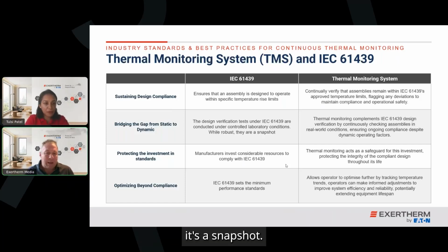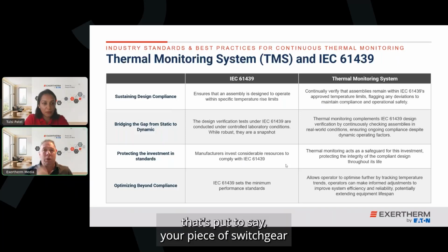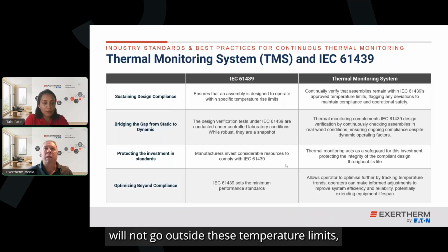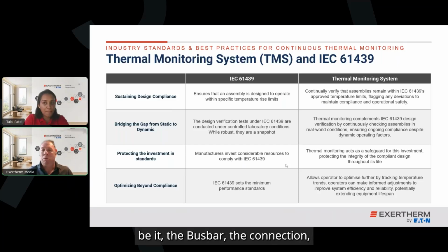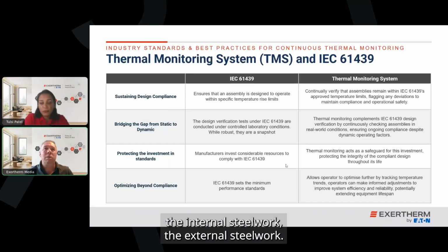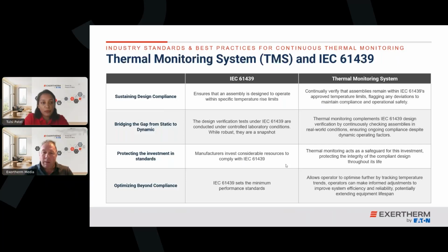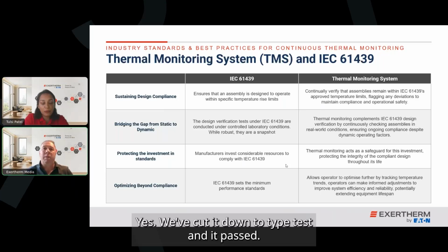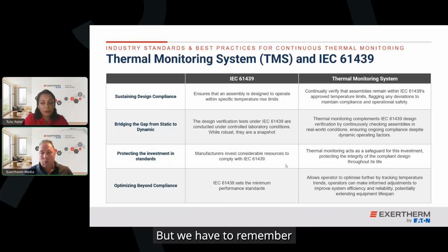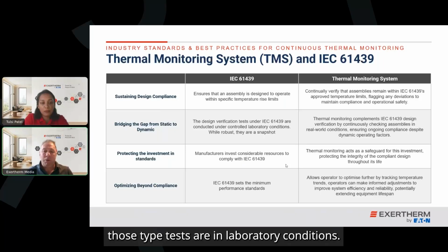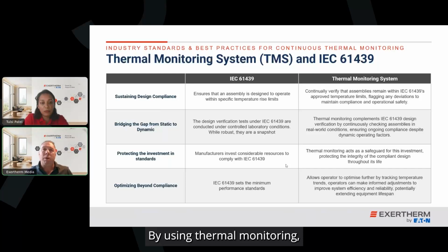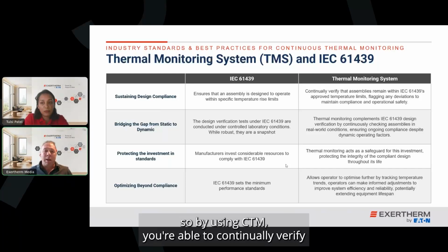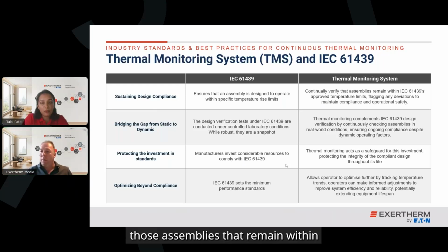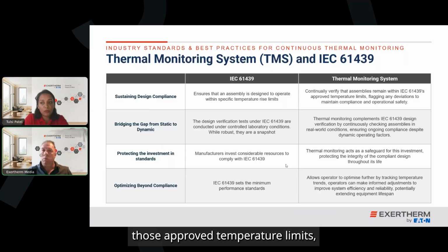Now, it's a snapshot. Yes, it's a design. It's a standard that's put there to say your piece of switchgear will not go outside these temperature limits, be it the bus bar, the connection, the internal steel work, the external steel work, anywhere. But it's a snapshot. Yes, it complies. Yes, we've carried out a type test and it passed. But we have to remember that those type tests are in laboratory conditions. By using thermal monitoring, so by using CTM, you're able to continually verify that those assemblies actually remain within those approved temperature limits.